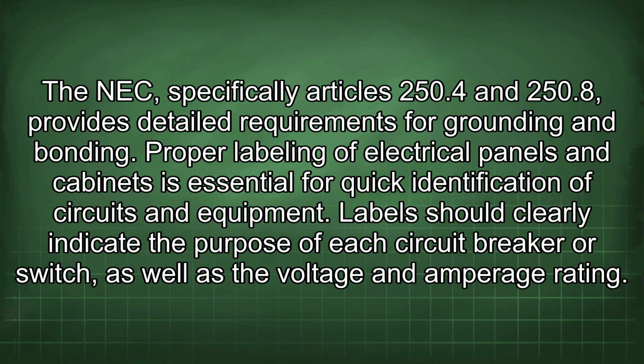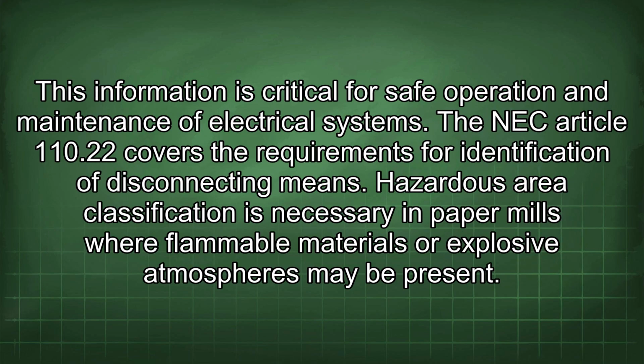Proper labeling of electrical panels and cabinets is essential for quick identification of circuits and equipment. Labels should clearly indicate the purpose of each circuit breaker or switch, as well as the voltage and amperage rating. This information is critical for safe operation and maintenance of electrical systems. The NEC Article 110.22 covers the requirements for identification of disconnecting means.